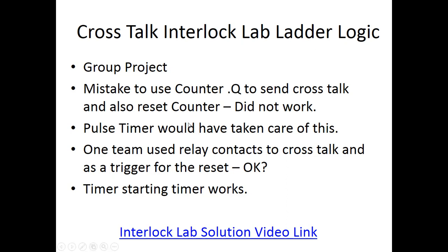But it wouldn't reset immediately, because as soon as the pulse timer is made for one scan, it's going to go ahead and hold that crosstalk relay down for a quarter second. And then using the relay contacts as a crosstalk and trigger for the reset is a pretty good idea.